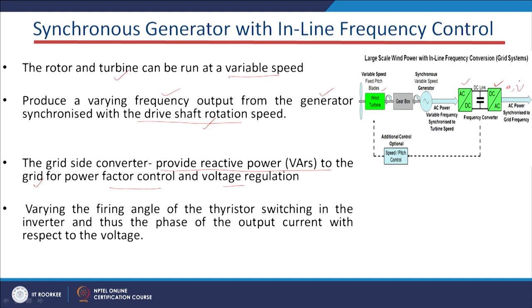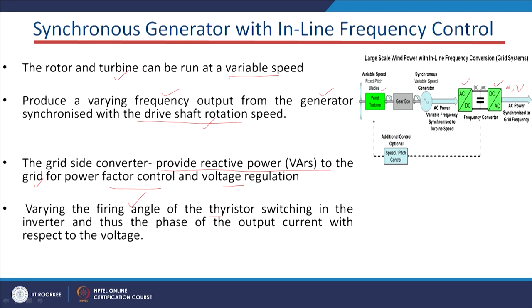In power electronic devices we have thyristors or IGBTs. By controlling the firing angle of these devices we can control the voltage and power factor. By varying the firing angle of the thyristor switching in the inverter, the phase of the output current with respect to the voltage can also be controlled — that is, we can control the phase angle between current and voltage of the grid side at the PCC.